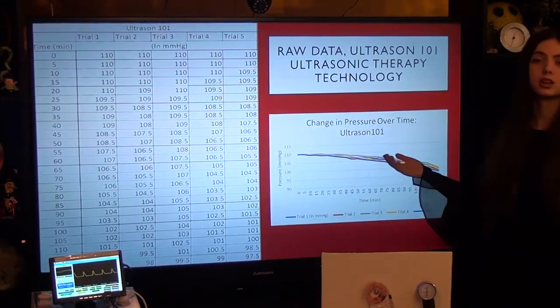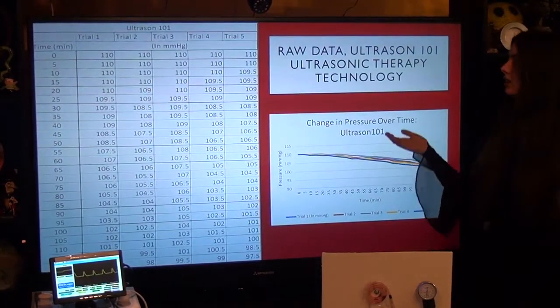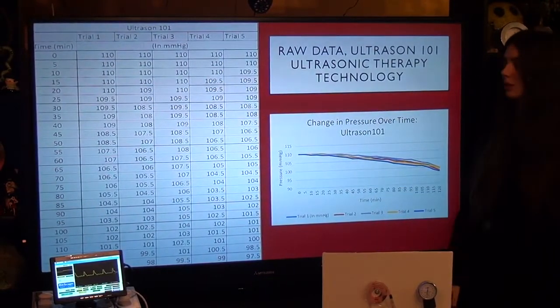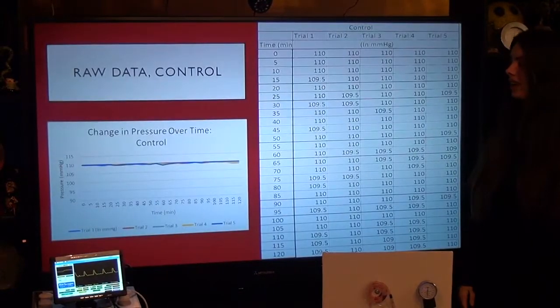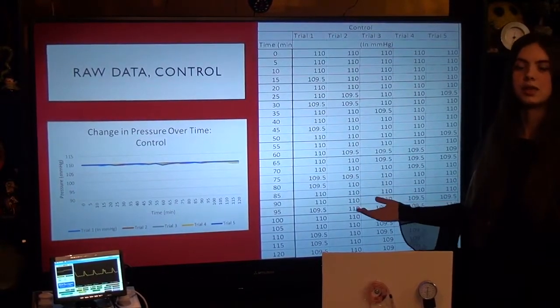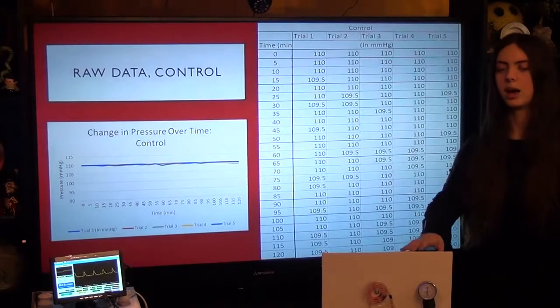Here we have the raw data for the commercial available method, the Ultrason 101, and you can see the pressure decrease over 120 minute period. And here we have the raw data for the control where no ultrasonic technology method was applied to the apparatus.